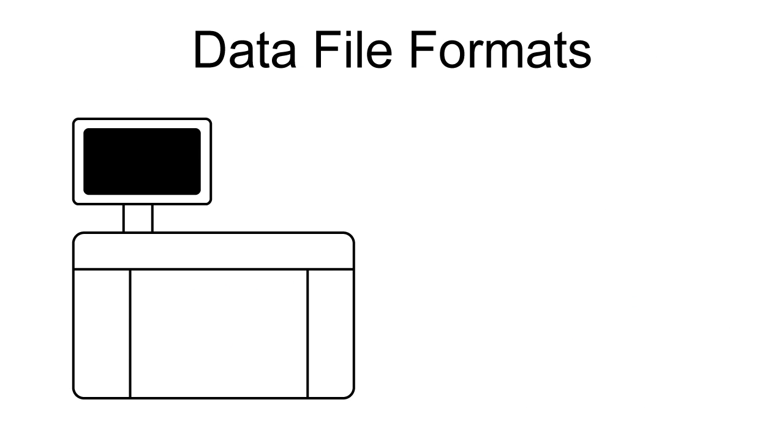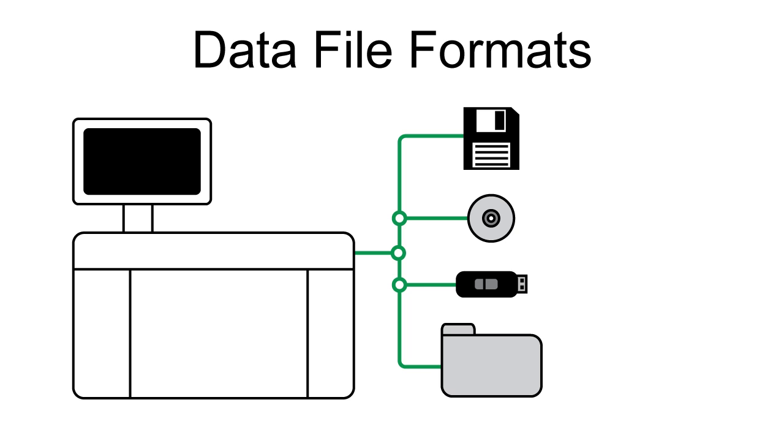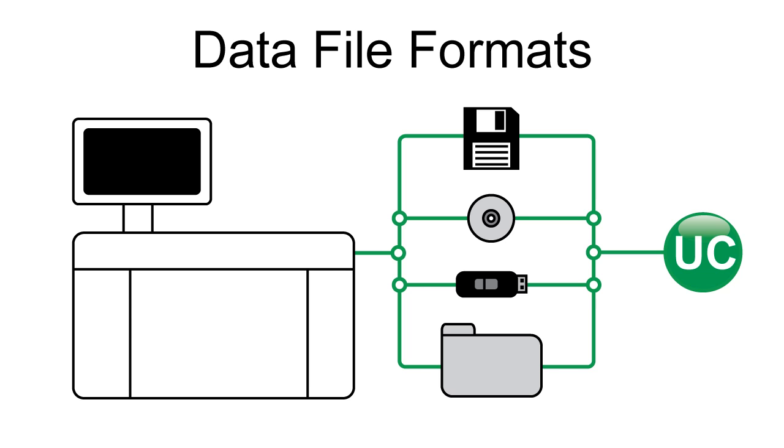Let's get a better understanding of how UnityConnect can capture data using a data file. At their laboratory system, the operator generates QC data. Depending on the make and model of the laboratory system, the data might be saved to a floppy disk, CD, flash drive, or a folder located on a local or network drive. The QC data can then be picked up by UnityConnect.